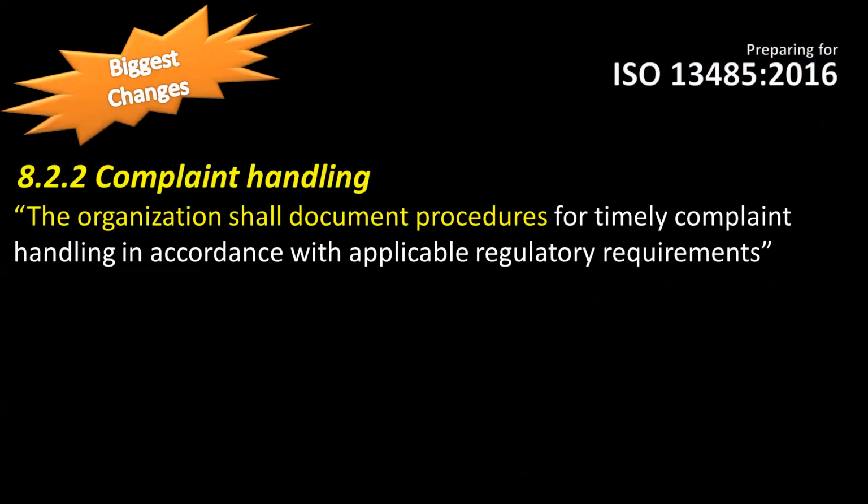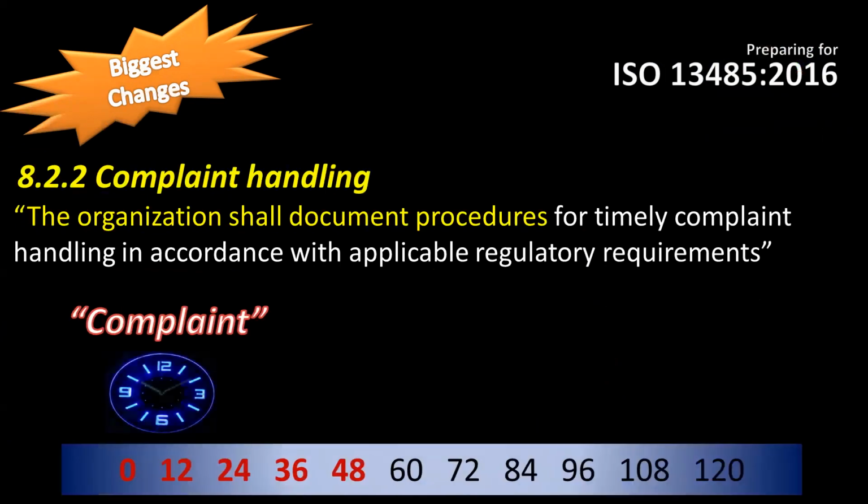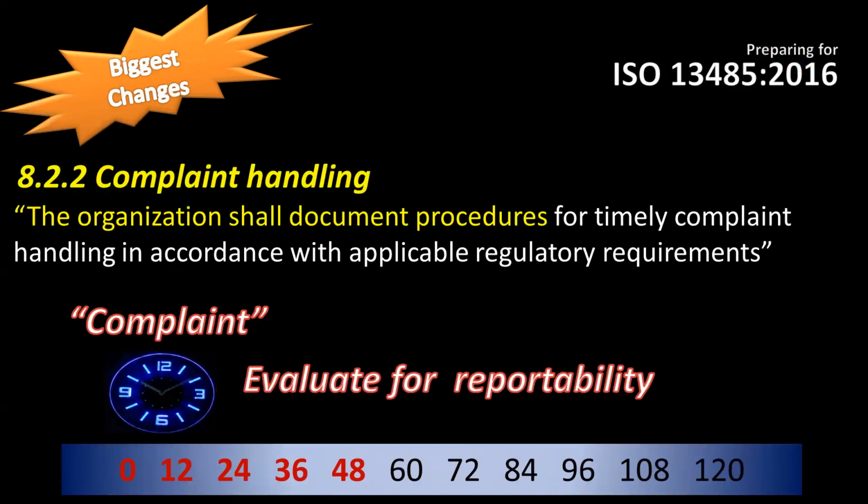Complaint handling. This is a brand new section of the standard, and it says that there shall be a documented procedure for timely complaint handling in accordance with applicable regulatory requirements. So a lot of jurisdictions, regulatory authorities, they do have a time frame for reporting serious injuries or death.